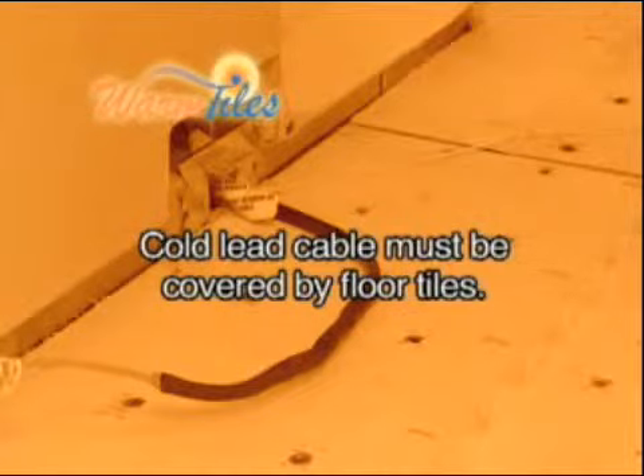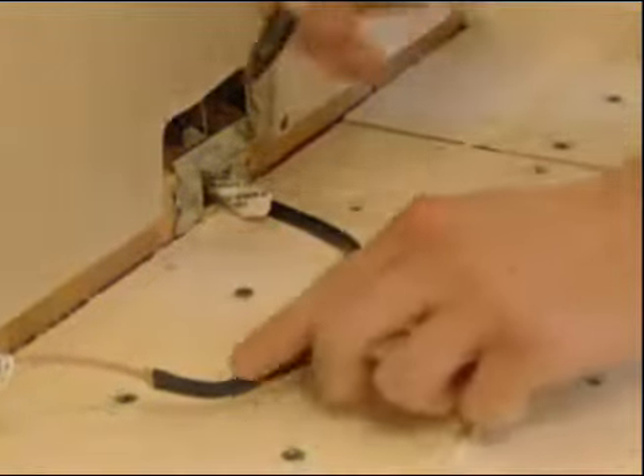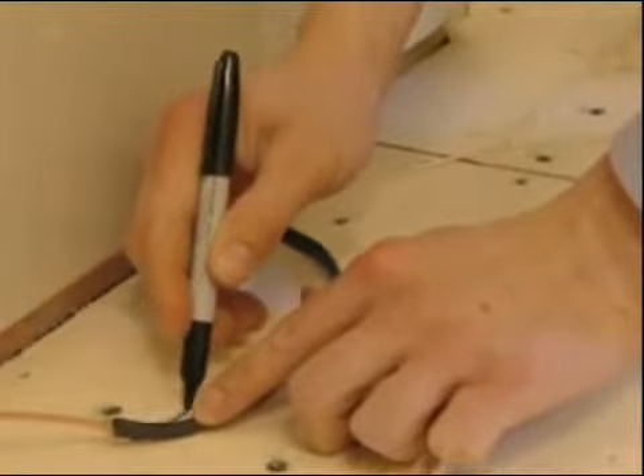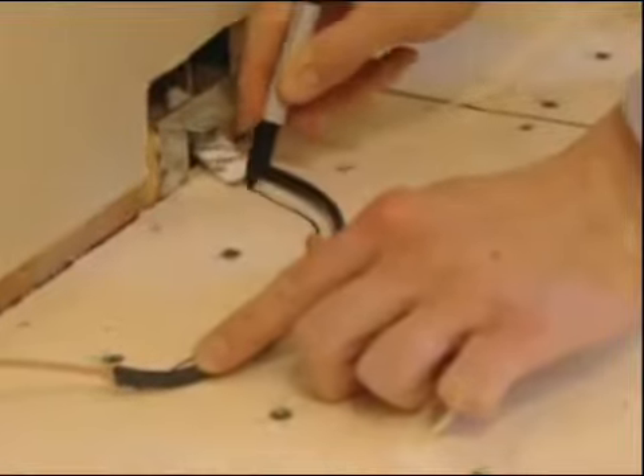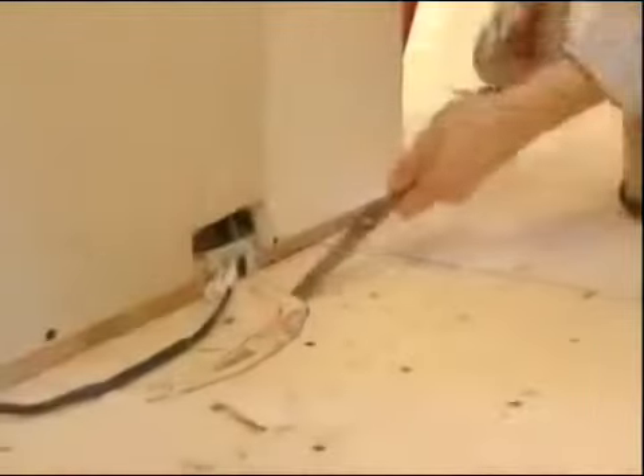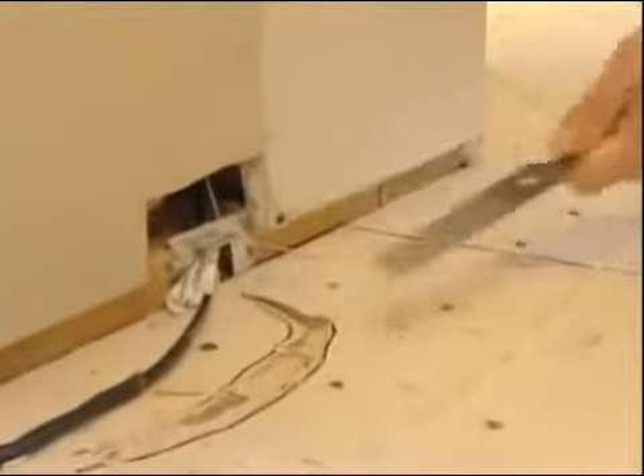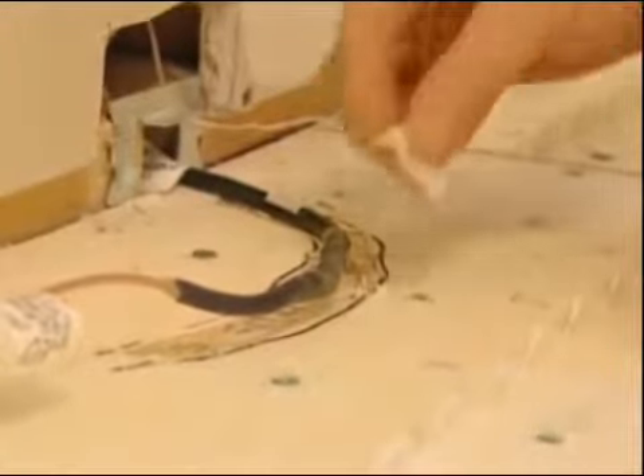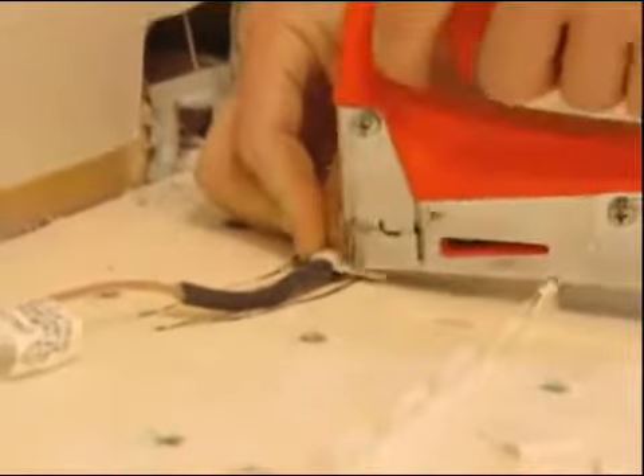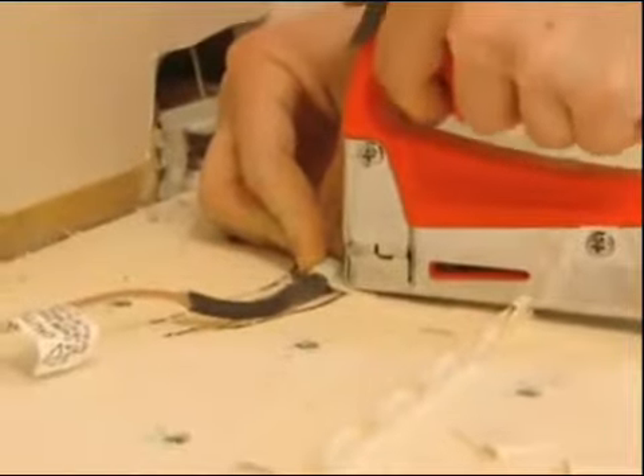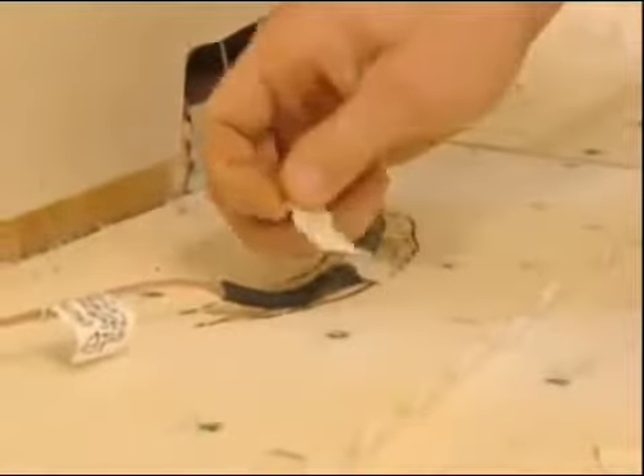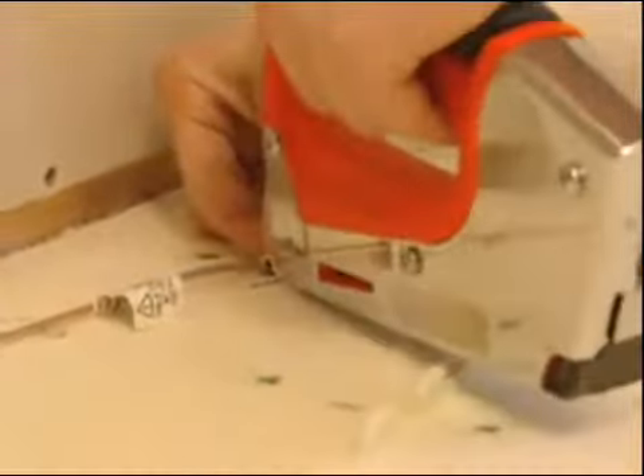Position the cold lead heating cable splice so that it will be completely covered by mortar or floor tiles. Recess the cold lead heating cable splice to the same height as the copper heating cable. The plywood may need to be carved to a depth of 1/4 inch. The cold lead heating cable splice is fastened to the floor using the clips included with the Warm Tiles cable kit.